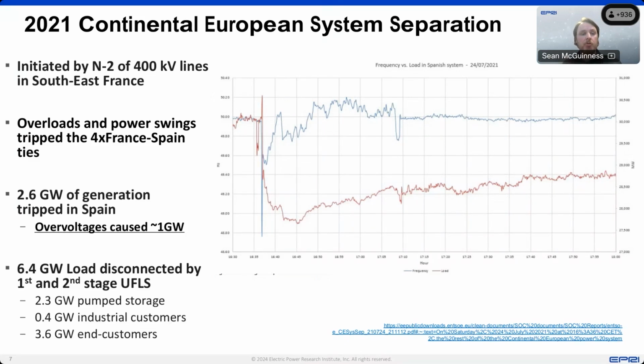And that second tripping led to overloading of the tie lines between France and Spain, and then power swings, and that tripped the connectors in between France and Spain. However, what happened next was probably the more interesting part of that. So after that loss of 2.5 gigawatts plus the remaining interconnectors, about 2.6 gigawatts of generators in Spain tripped, on top of the existing loss of imports. But of that 2.6 gigawatts, about 1 gigawatt tripped due to overvoltages. So traditionally, when we see blackouts and cascade tripping, we see synchronous generators tripping due to underfrequency, volts per hertz or overexcitation protection, and out-of-step protection and other protection functions. But it was relatively unusual to see so many generators trip purely due to overvoltages. And we'll explain those in a moment.